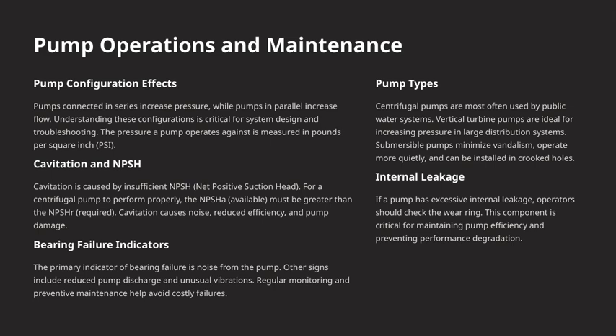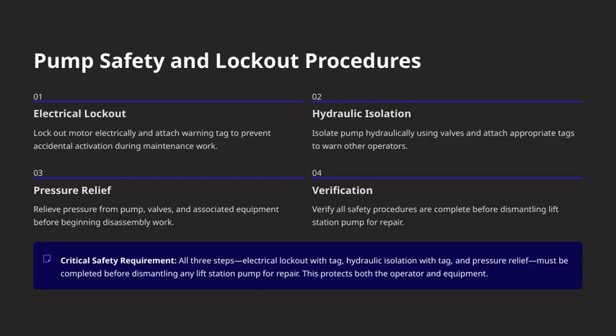Lastly, internal leakage is another factor to keep an eye on. If you notice performance degradation, it could be due to excessive internal leakage, often caused by wear in the wear ring. Checking and maintaining this component is vital for keeping your pump running efficiently and avoiding bigger problems down the road. All these points tie back to our overall goal: ensuring pump systems operate reliably, efficiently, and safely through proper understanding, monitoring, and maintenance. Let's talk about pump safety and lockout procedures, which are essential for protecting both the team and the equipment.